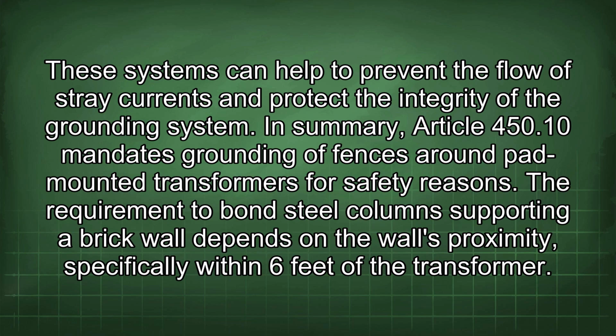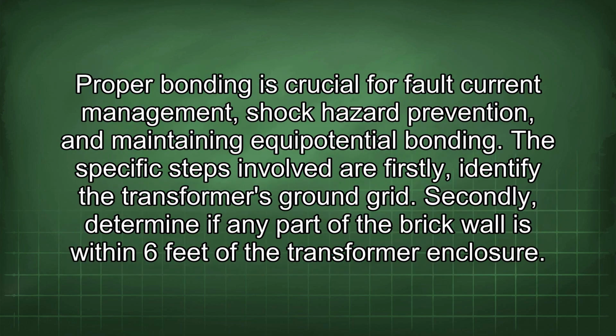These systems can help to prevent the flow of stray currents and protect the integrity of the grounding system. In summary, Article 450.10 mandates grounding of fences around pad-mounted transformers for safety reasons. The requirement to bond steel columns supporting a brick wall depends on the wall's proximity, specifically within 6 feet of the transformer. Proper bonding is crucial for fault current management, shock hazard prevention, and maintaining equipotential bonding.